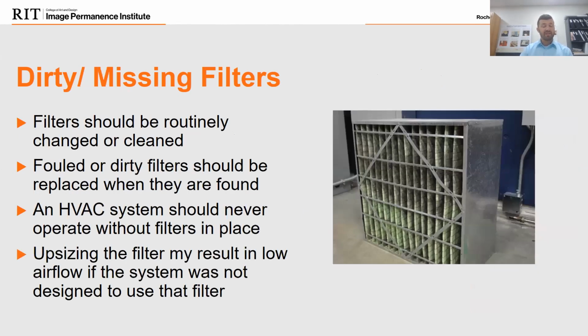Some dirty, missing filters as well. Filters should be changed and cleaned routinely. Fouled and dirty filters, replace them as you find them. I know this goes a lot to the facility staff, but it's something for collections to keep in mind. An HVAC system should never operate without its filters. And if you operate it without them, you're going to clog up your coils very quickly.